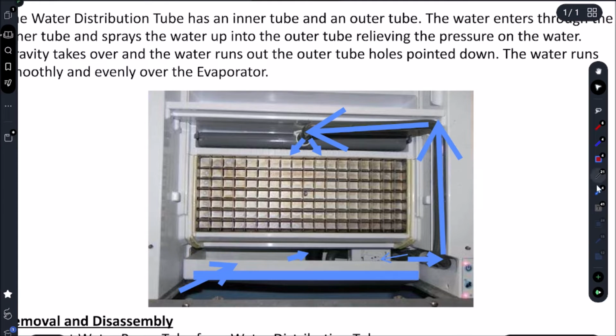Once it gets to a certain level, the contacts on the low water float will close, starting a harvest. So based on all that, we're looking at a potential pump issue, a potential refrigeration issue, and we're going to look at, is our low float closing? Is the water level in this trough actually dropping?